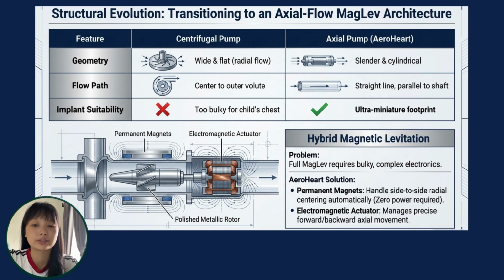compromising the surrounding organs. The axial pump is chosen for ultra-miniature design because of the trade-off between pressure and blood safety. Designing for ultra-miniature scale requires balancing between pressure and blood safety. As for size versus speed, because axial pumps are smaller, they need to spin at higher velocities in order to generate the necessary pressure. Next is the safety priority. In order to prevent hemolysis, which is the rupturing of red blood cells, the impeller design is meticulously optimized to maintain high flow rates without excessive rotational heat or friction.